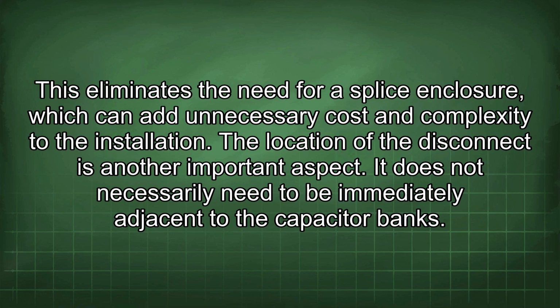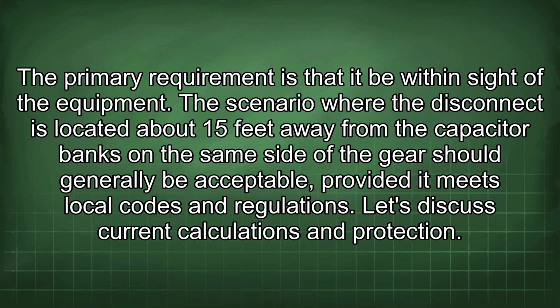The location of the disconnect is another important aspect. It does not necessarily need to be immediately adjacent to the capacitor banks. The primary requirement is that it be within sight of the equipment. The scenario where the disconnect is located about 15 feet away from the capacitor banks on the same side of the gear should generally be acceptable, provided it meets local codes and regulations.